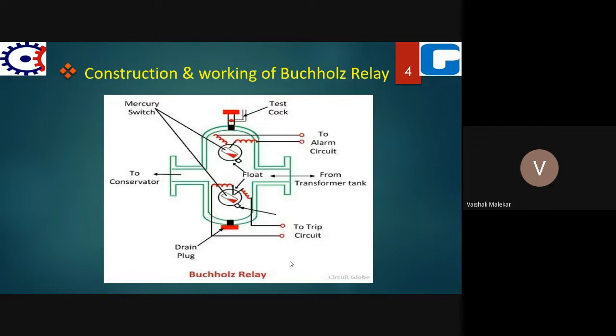Now we'll see the construction and working of this Buchholz relay. Where can this relay be used? It can be used in transformers which have conservators. It is placed in the pipe which connects the conservator with the transformer tank, and it consists of an oil filled chamber. You can see in the diagram, this chamber is completely filled with oil.